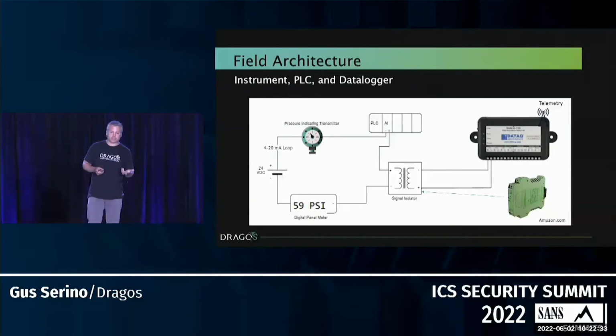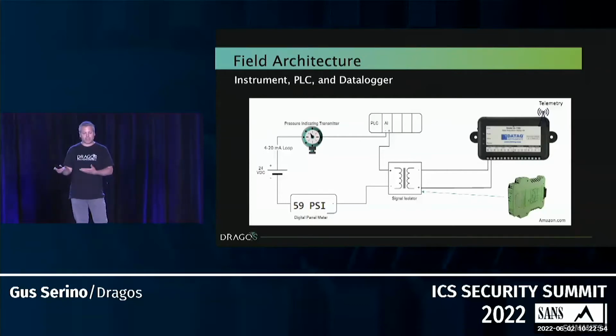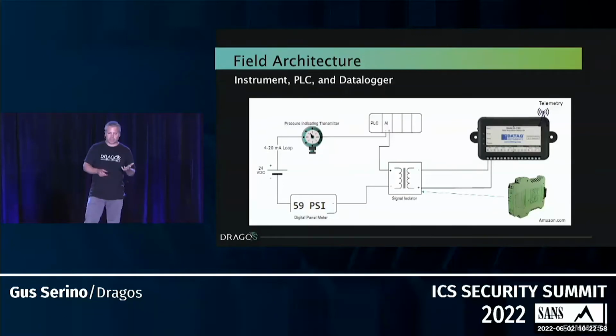This diagram is the field side of that. On the left-hand side, we have a traditional 4 to 20 milliamp loop. You see the 24 volt power supply, sending DC current through the pressure transmitter up to the PLC, then through the signal isolator, which I'll talk about in a second, through a digital panel meter, which is basically a local indication at the site of that value, and then completing the loop back to the DC power supply. That's the primary 4 to 20 milliamp loop.